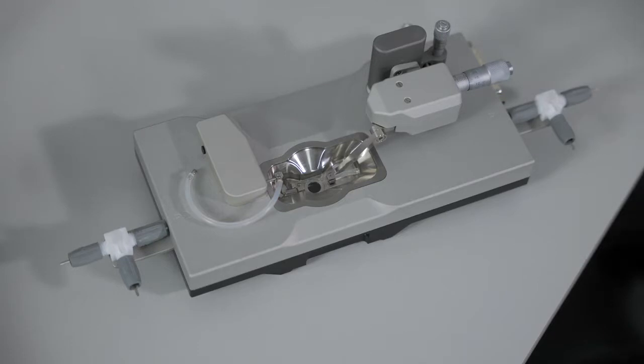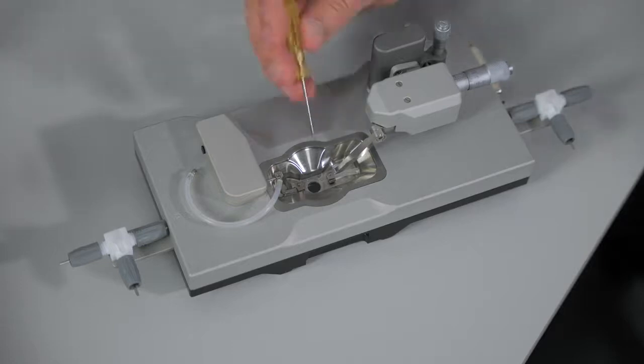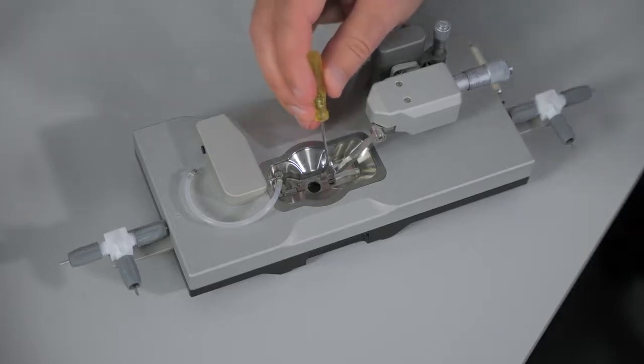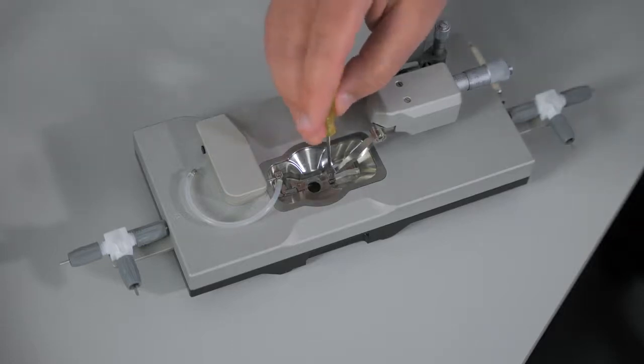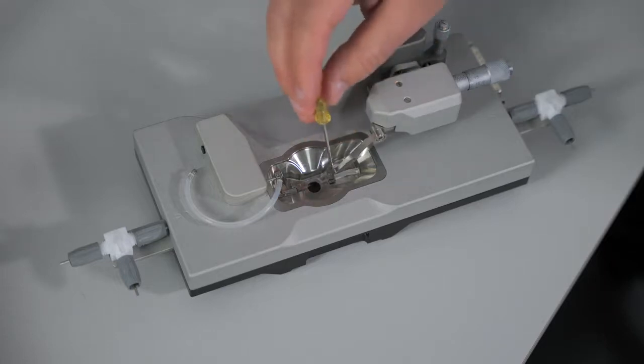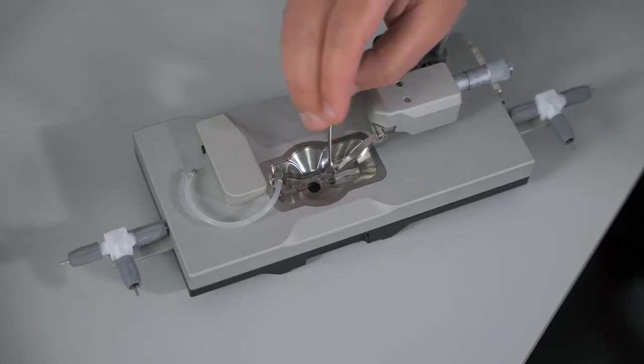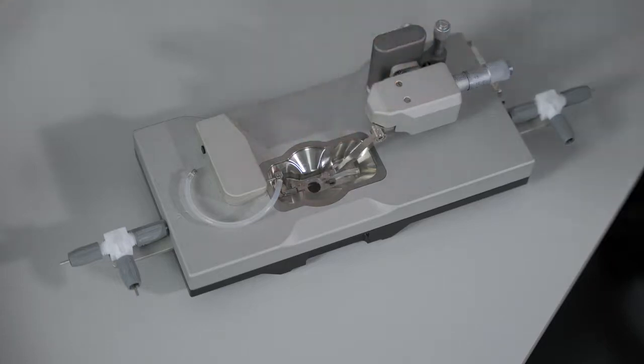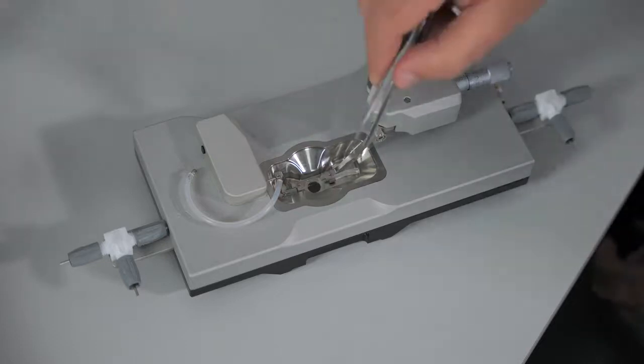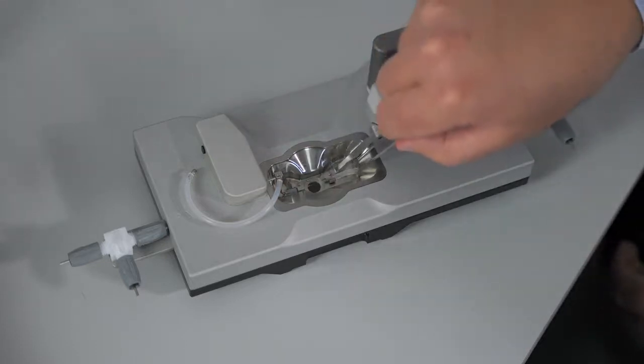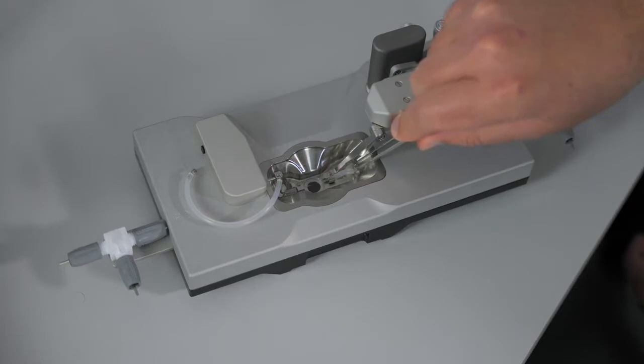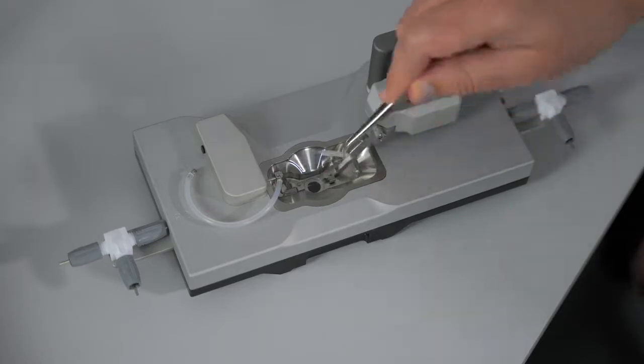The process for replacing the cannulas will differ depending on which side you are replacing. If you're replacing the right side, which is the micropositioner side, you will first need to loosen this screw which holds the plate in place which secures your cannula. Then, using a pair of forceps, you will remove the tubing from the port on the chamber.